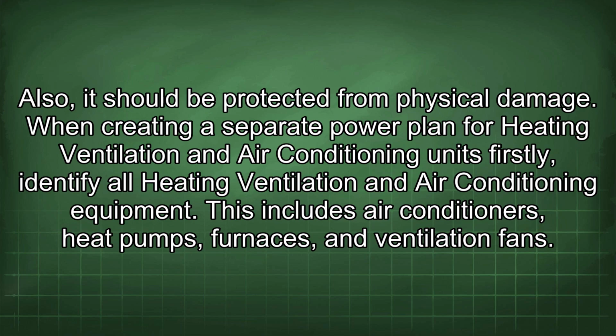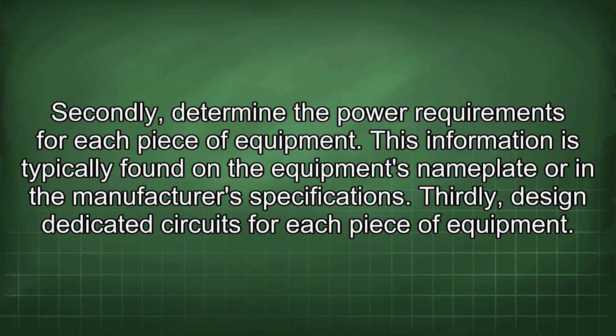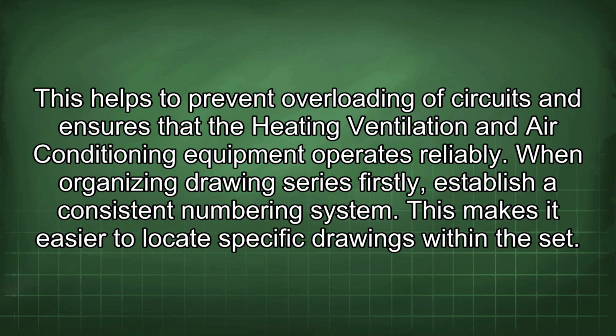When creating a separate power plan for heating, ventilation, and air conditioning units, firstly, identify all heating, ventilation, and air conditioning equipment. This includes air conditioners, heat pumps, furnaces, and ventilation fans. Secondly, determine the power requirements for each piece of equipment. This information is typically found in the equipment's nameplate or in the manufacturer's specifications. Thirdly, design dedicated circuits for each piece of equipment. This helps to prevent overloading of circuits and ensures that the heating, ventilation, and air conditioning equipment operates reliably.